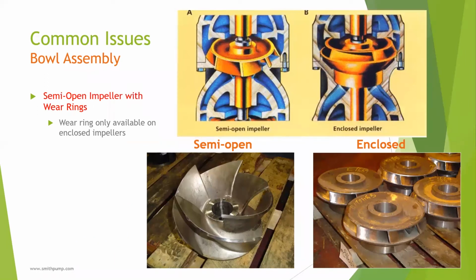Wear rings are a great addition to a pump spec, but not all pumps can use wear rings. Only the enclosed impellers can utilize wear rings because their design has a landing on the suction side for the wear ring installation, shown here.